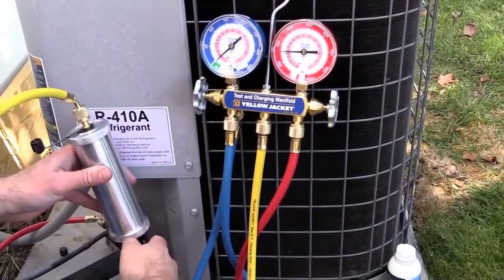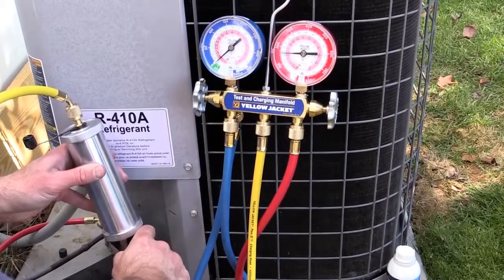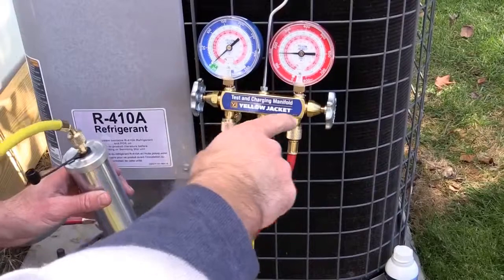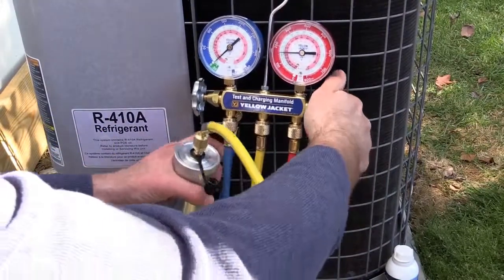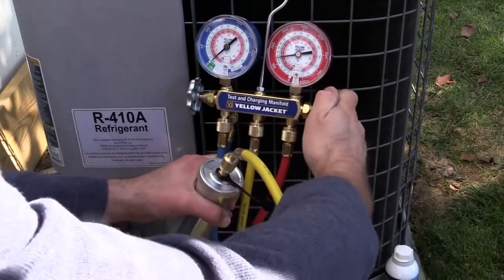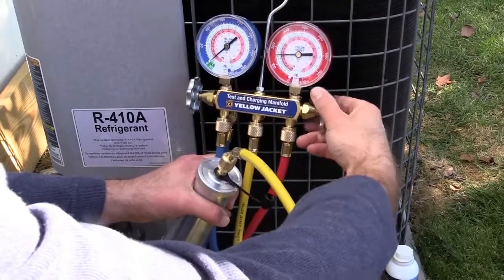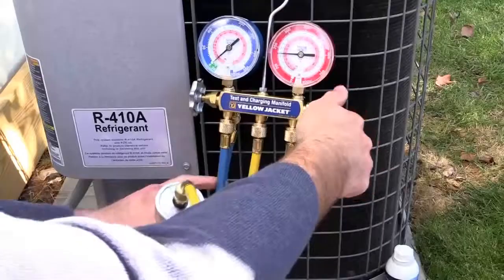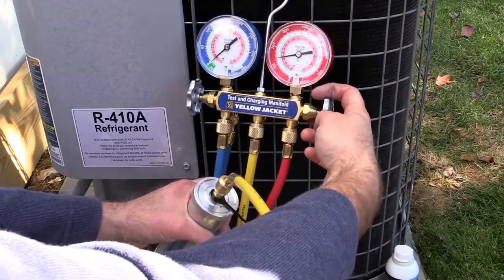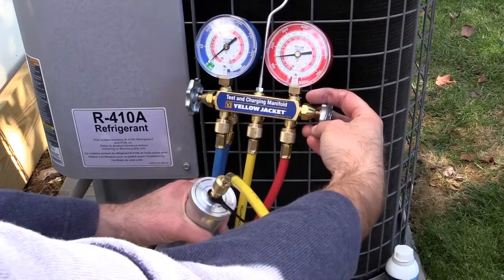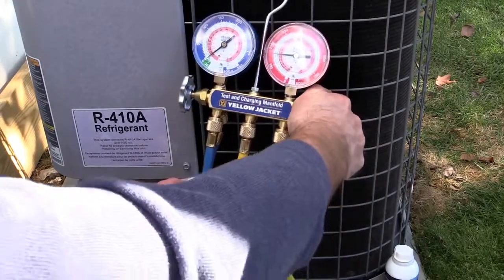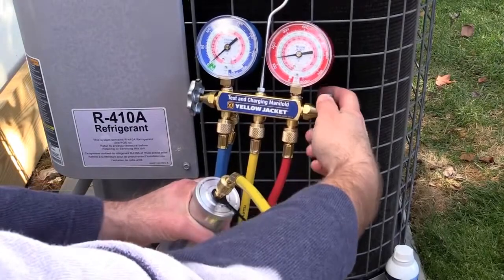Open the injector tool's hand valve to allow AC Renew to flow from the injector into the low side of the system. Briefly open the high side valve of the manifold gauge set to allow a small amount of high side liquid to flow through the yellow hose and injector. Close the high side manifold valve. Repeat this process for a total of 1 minute of manifold valve open time to ensure AC Renew is fully injected into the low side of the system.